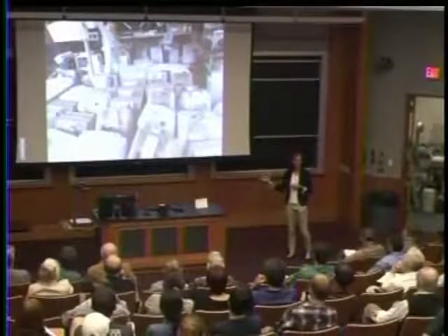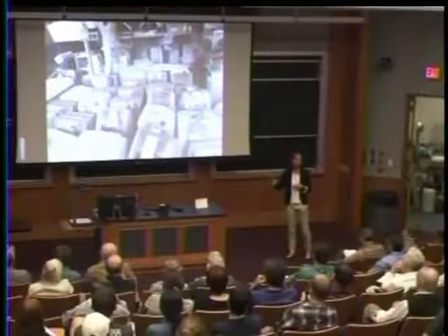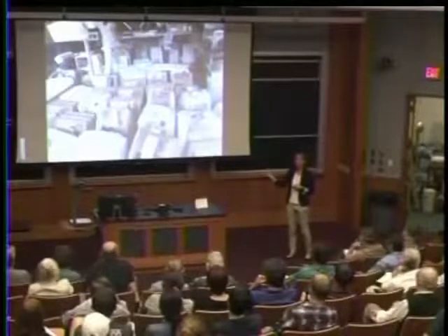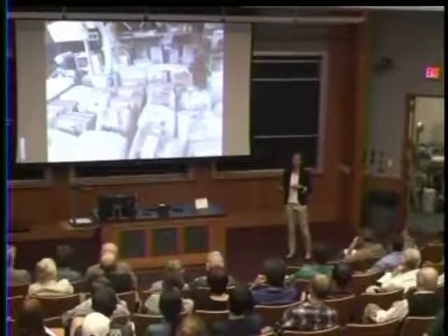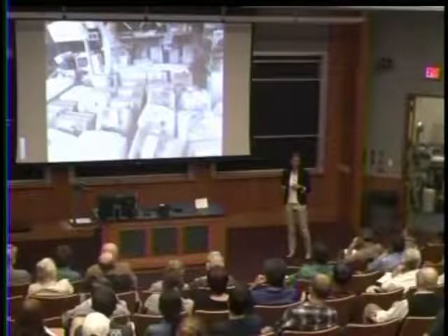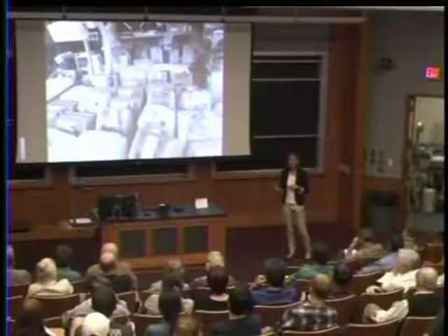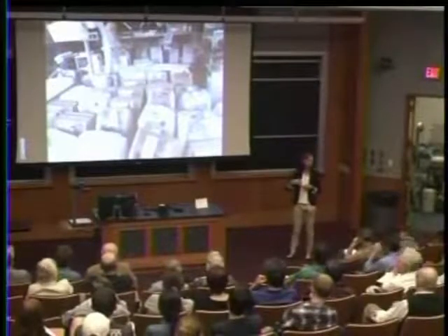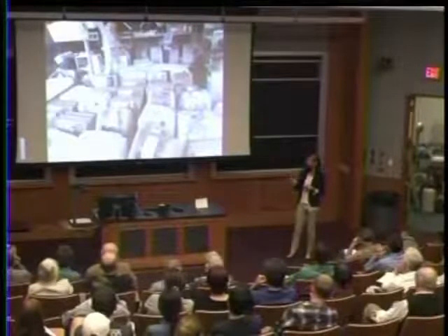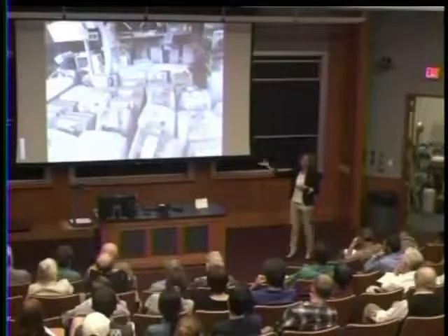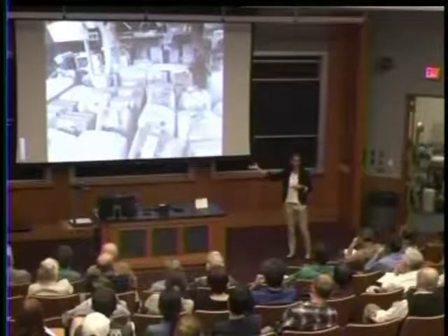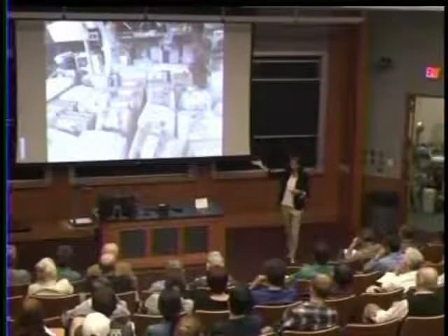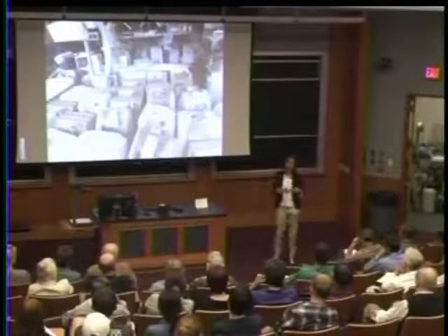And it is full of equipment that has been donated by people who really wanted to help improve the situation there. And then that equipment gets plugged into an electrical system where you've got large line voltage spikes. It's operated in an environment that's not air conditioned, where the windows are open, it's very humid, it's very dusty, there might be insects, there might be rats, and they quickly fail. And so in this room were 83 broken oxygen concentrators. And if any one of those oxygen concentrators worked, it would have been being used in the NICU.